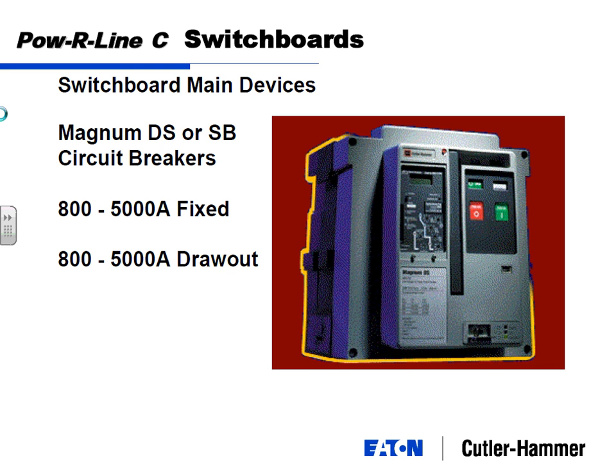In addition to being barriered and compartmented, each circuit breaker is individually barriered and compartmented. The horizontal bussing is individually barriered and compartmented, and the cable compartment is barriered and compartmented. So all these different things keep any faults isolated as best as possible to the location of the fault, without taking down everything next to it, or greatly lessening the chance of taking down something next to it. So the switchgear is designed to withstand 30 cycles of fault currents.